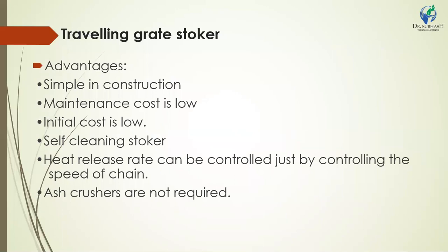It is very simple in construction and the initial cost is very low. It is reliable and the service and maintenance cost is very low. It gives a high heat release rate per unit volume of furnace. The heat rate can be controlled by the speed of the chain. It is a self-cleaning stoker and ash crushers are not required as clinkers are not formed.